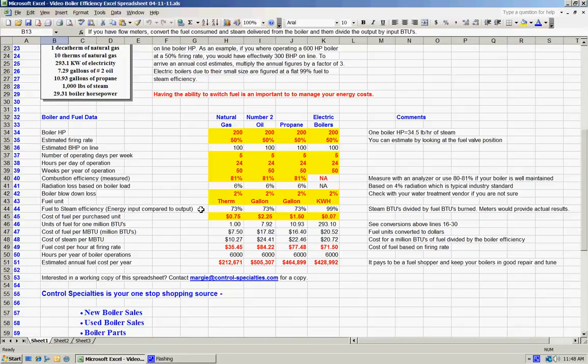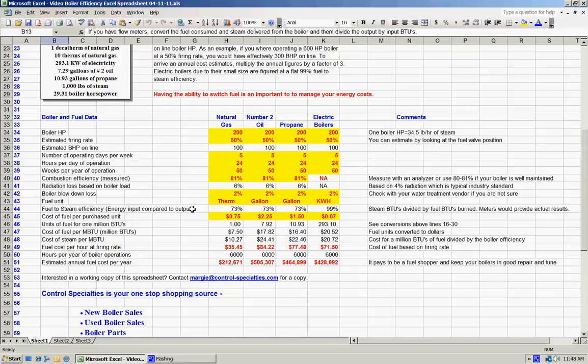Line 44 then becomes just a calculation of taking the combustion efficiency and subtracting out the radiation losses and the blowdown losses and that's the result of those calculations. For the electric boiler, we've scored a consistent 99 percent and that's really a pretty fair number for an electric boiler since there are no stack losses, basically just the radiation off the boiler box itself, which is pretty small.